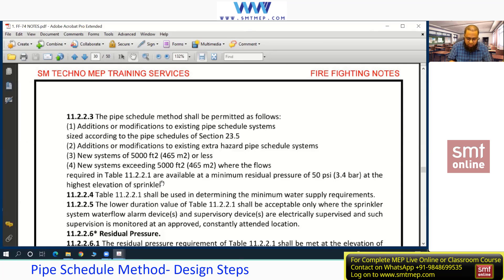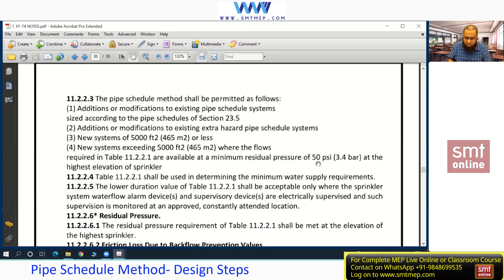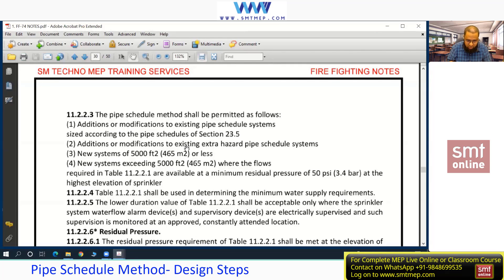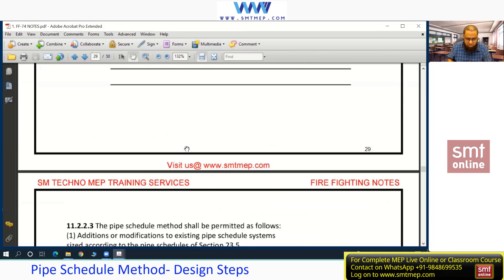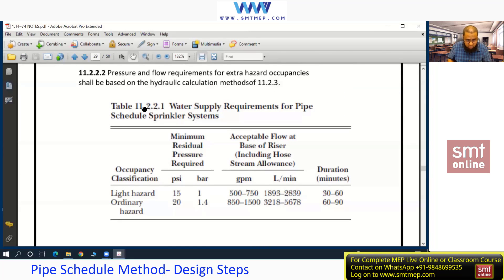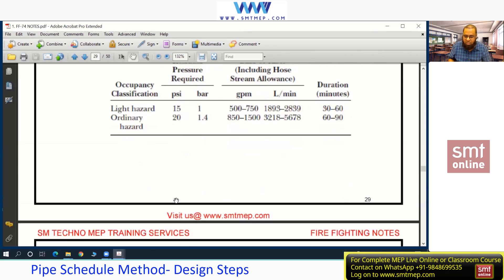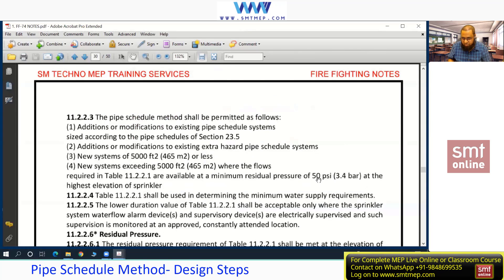For a new system, it must be not more than 5,000 square feet. As per the authority having jurisdiction (AHJ), if they allow the pipe schedule method above 5,000 square feet, the residual pressure must be maintained at 50 psi. In normal conditions — area less than 5,000 square feet — we follow the residual pressure given in Table 11.2.2.1: 15 psi for light hazard and 20 psi for ordinary hazard. Extra hazard is not listed, but if you use pipe schedule for extra hazard, the residual pressure should be 50 psi.